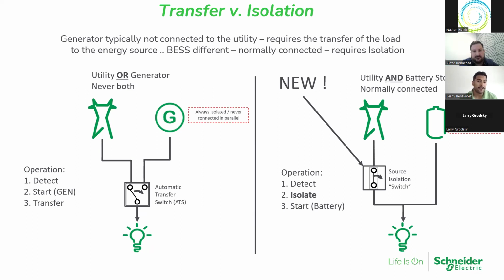Whereas an isolation switch is utility and battery storage. Remember, the two are both connected. Batteries act as a load. They can also serve as a power source. So during normal operation, your battery energy storage system is acting as a load, or projecting current into your system to offset utility costs. And the key distinguishing point here with an isolation switch is that it detects the utility outage, much like a transfer switch. It has a controller that monitors voltage and frequency.